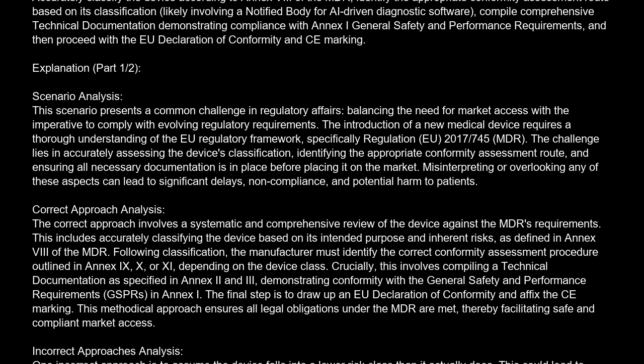Misinterpreting or overlooking any of these aspects can lead to significant delays, noncompliance, and potential harm to patients. Correct approach analysis. The correct approach involves a systematic and comprehensive review of the device against the MDR's requirements.